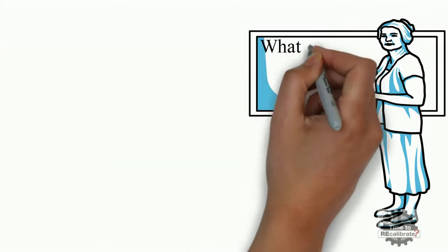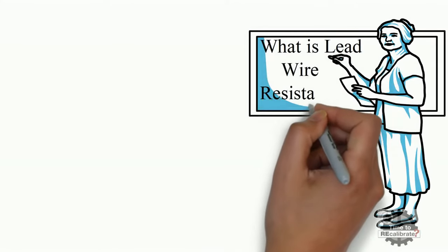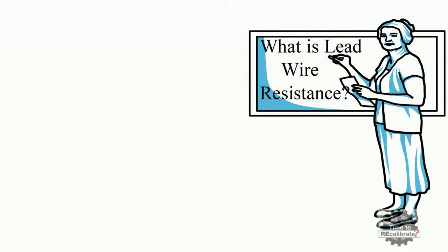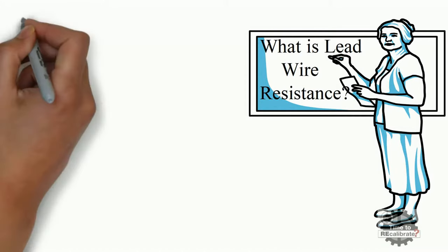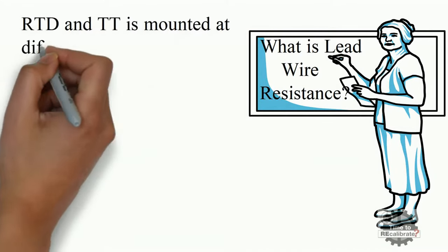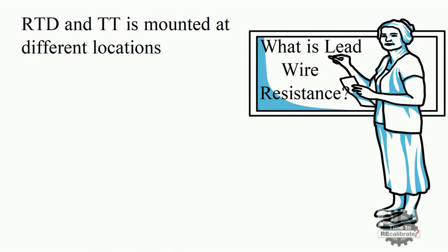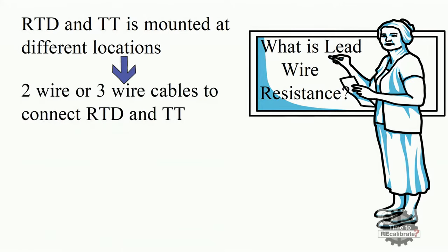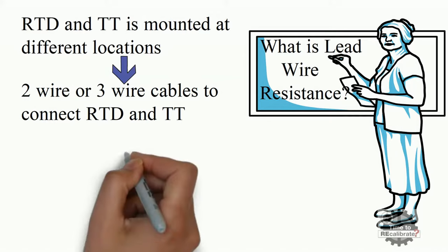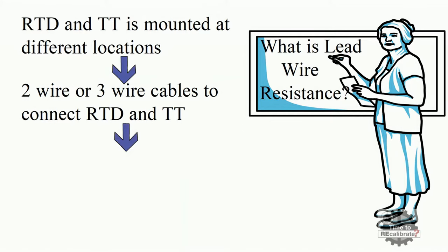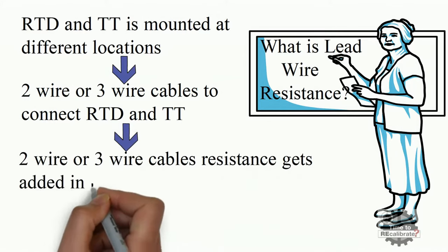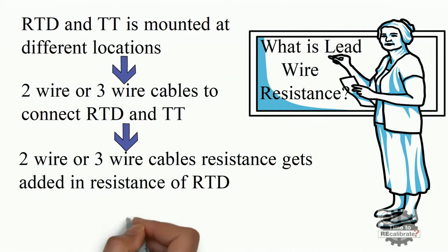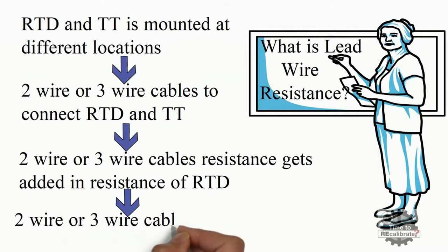Let's learn what is lead wire resistance in 2-wire RTD. As we know, in practical applications, RTD and temperature transmitter are mounted at different locations. So we use 2-wire or 3-wire cables to connect RTD and temperature transmitter. These cables have their own resistance, which gets added to the resistance of the RTD. This cable resistance is known as lead wire resistance.